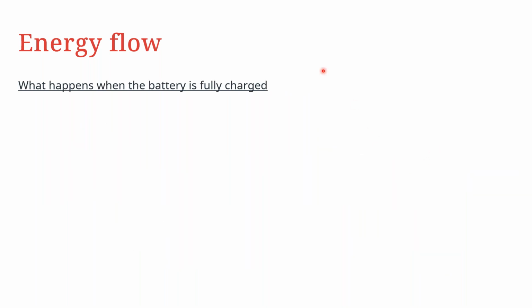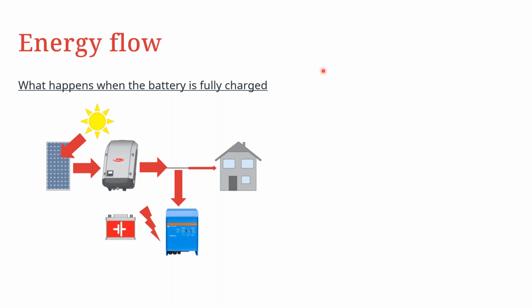In addition to that, we also need to make sure that when the battery is fully charged, the Victron inverter is able to react in a manner that triggers the Fronius inverter to either increase or reduce the power output or power production. So in this case, we can see that we still have very high production from the PV side. A lot of this is being converted by the Fronius inverter, some of it going to the loads, but in this case we have the battery at near full state of charge.